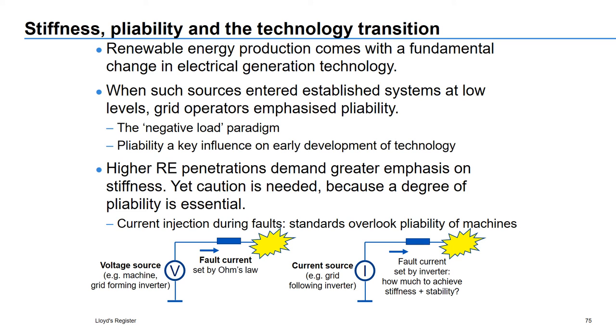It's useful to look at the interplay between stiffness and pliability concepts with the transition to renewable energy and the fundamental technology change this represents from historically synchronous machines to equipment that tends to operate on electronic principles, such as in inverters. While these new technologies were only a small proportion of the total generation in the system, when we're talking about 20 years ago, for example, the system operators at the time found it useful to emphasise pliability. The reason was that there was well understood behaviour from the synchronous machines in the system, which were still doing the heavy lifting. The new technology should, for proper operation of the network, just follow what the synchronous machines were doing. So pliability ensured that they would just follow those changes.